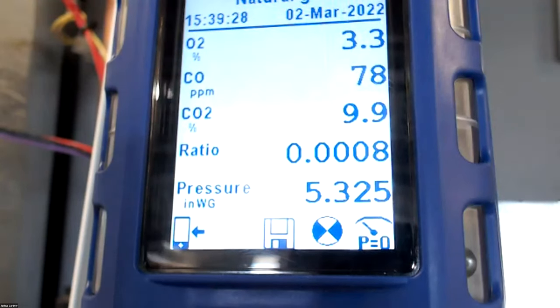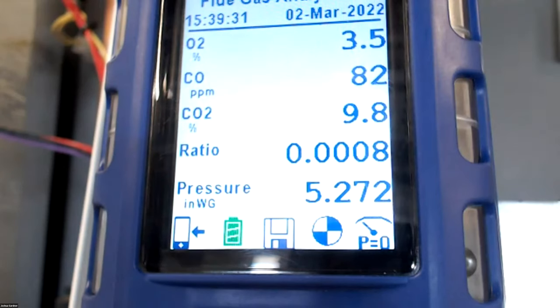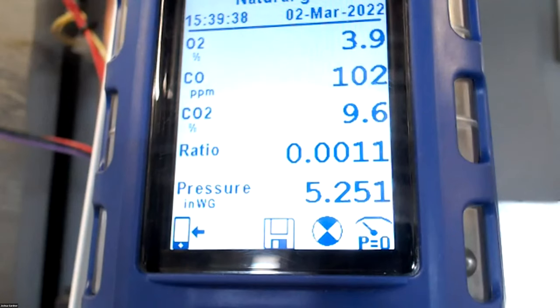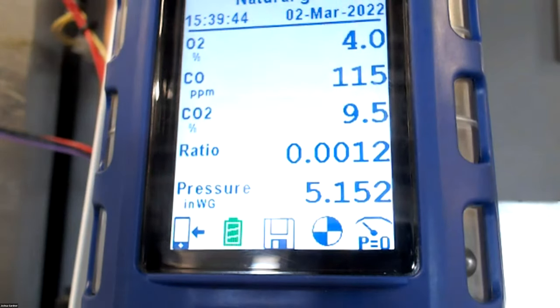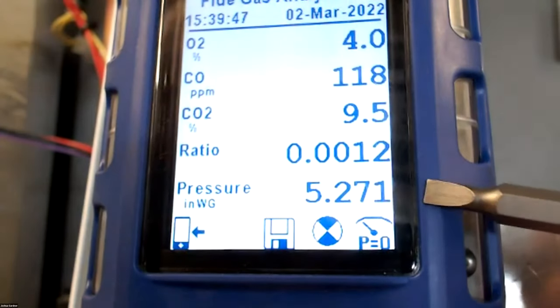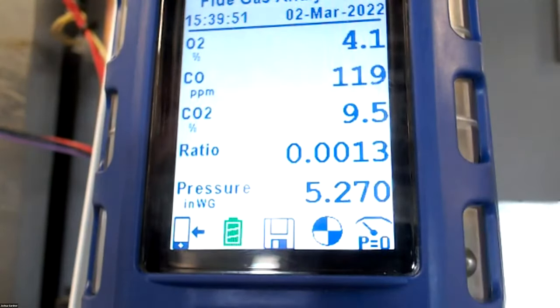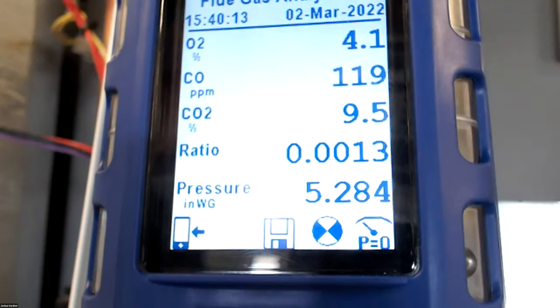Now I'm at 100%. Again, my target on the top line: O2 I'm looking for 3.95, CO2 9.5, and my CO below 150. I haven't dropped below 5, and I don't think I dropped more than an inch. Close, but we're good. We're in there. All right, so it looks like we flattened out right there and stabilized.